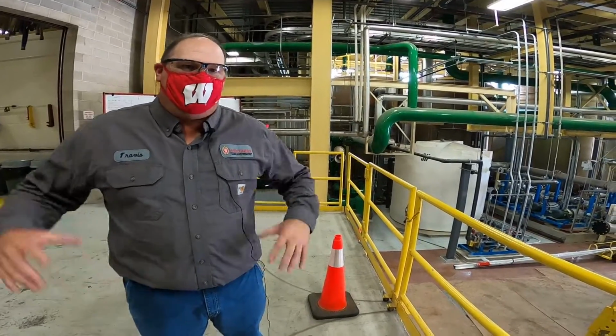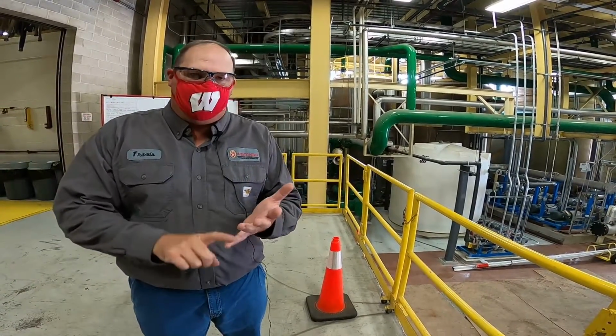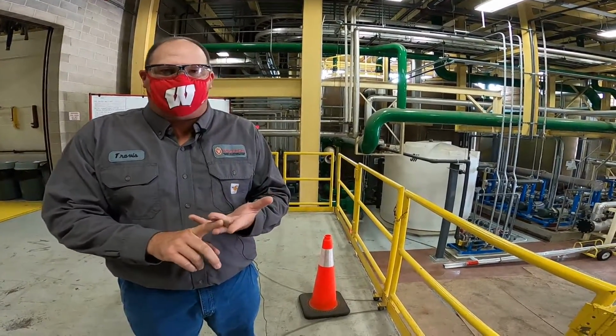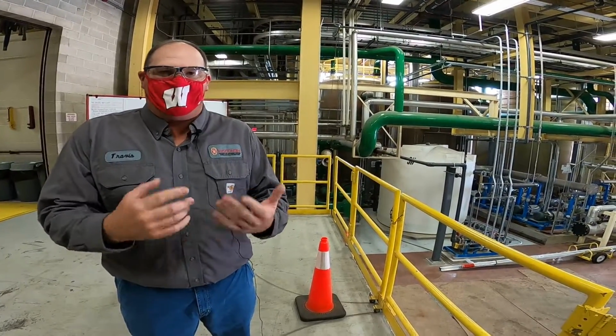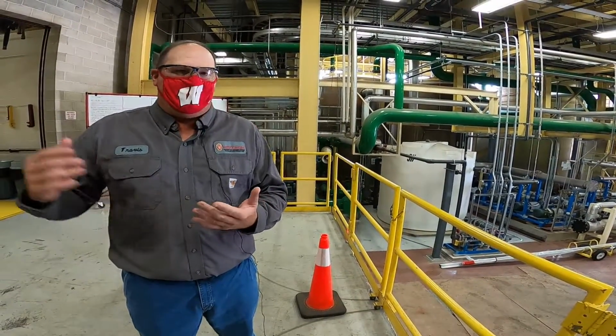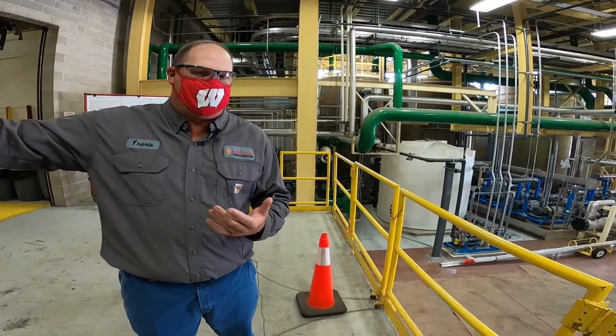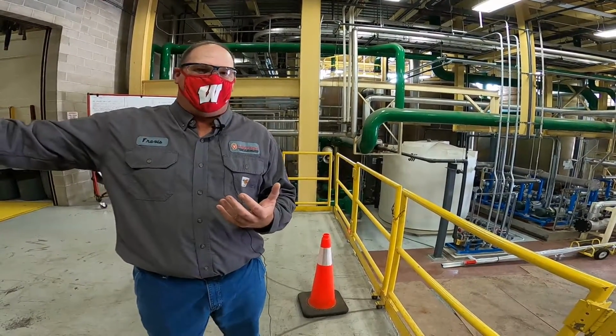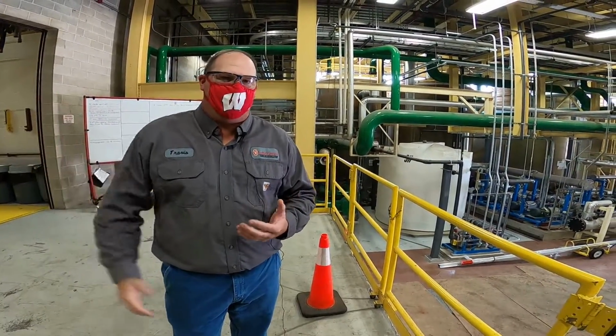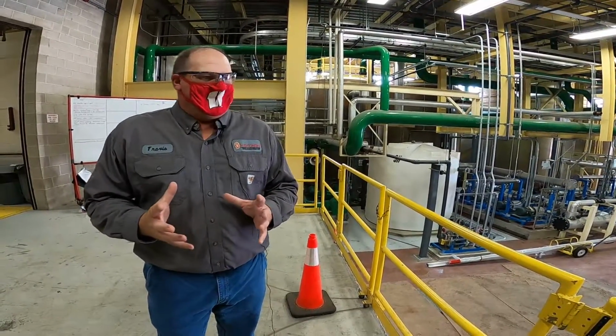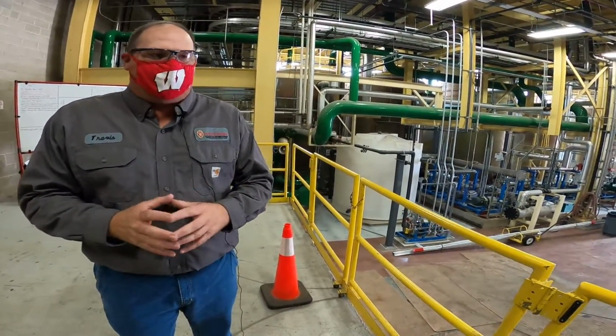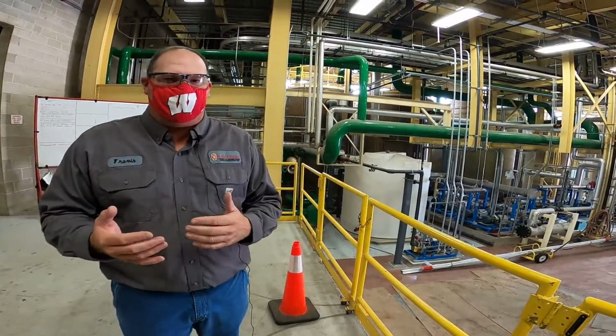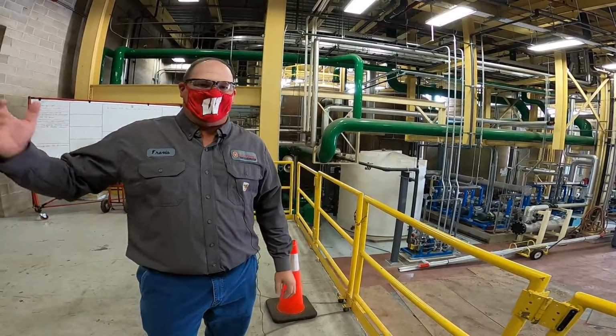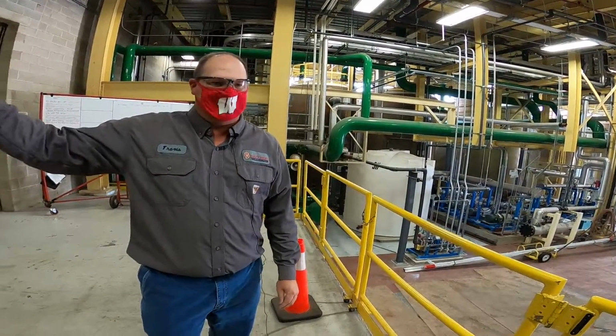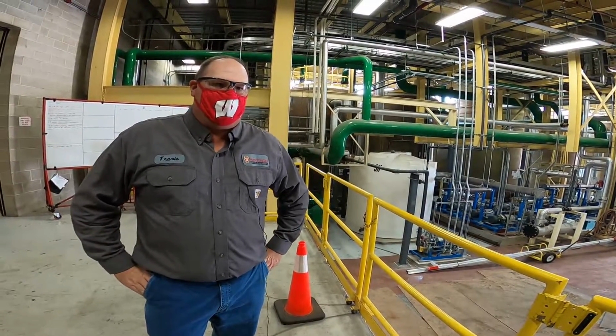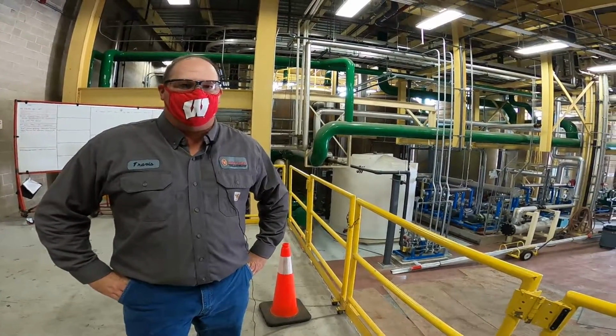So obviously, you know, the condensate is also pure. It's the purest form of water. There's no minerals per se in it. We put some chemicals in it to protect the carbon steel pipe that allows that to come back to the plant. It's an amine, and it produces a film on that pipe to protect it so it'll last 50 years or more. But that's about it. And it's just, we got to capture that condensate, otherwise we won't be sustainable.